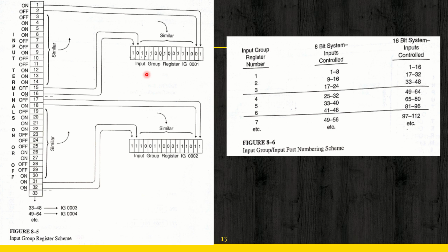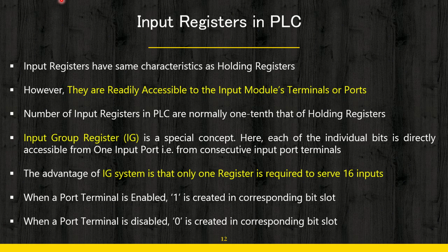But whenever we are talking of the register, it is one whole register, and therefore it is being called a group register. Now a group register has only one address. You are not independently addressing this register or this register. You are talking of the complete 16 bits as a whole, as a group register. So this helps you in saving memory space in your computational device.